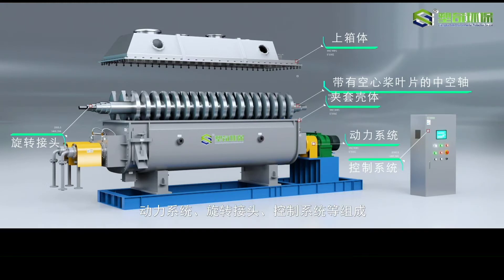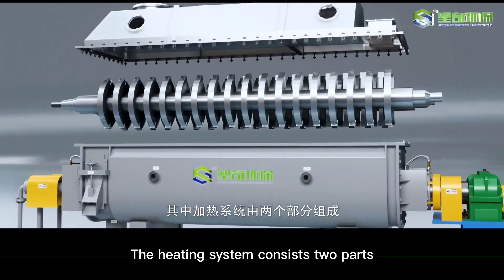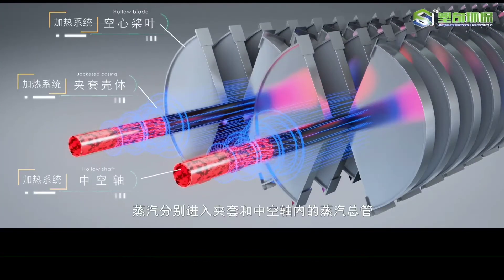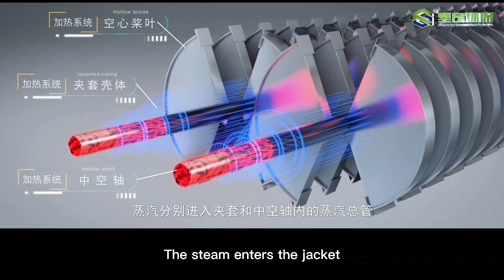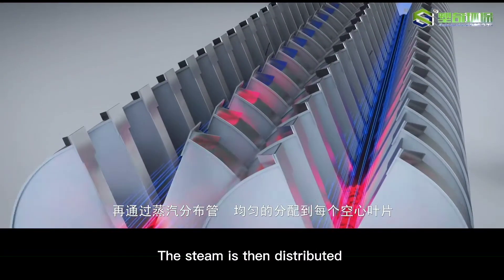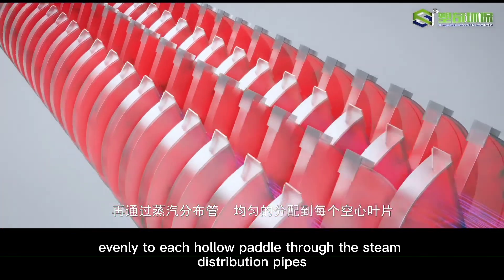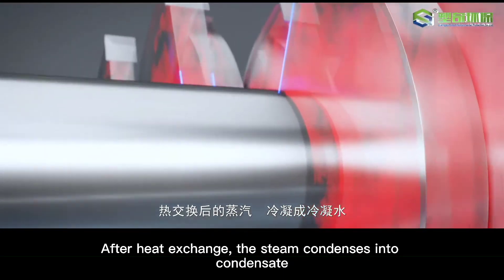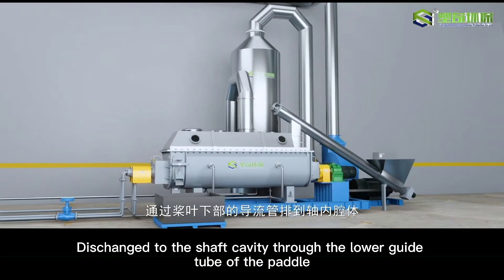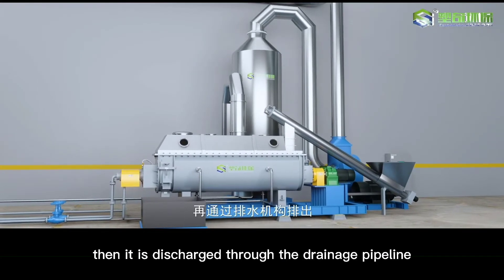The heating system consists of two parts: the jacketed casing and the hollow shaft consisting of hollow paddles. Steam enters the jacket and the steam main pipe inside the hollow shaft. The steam is then distributed evenly to each hollow paddle through the steam distribution tube. After heat exchange, the steam condenses into condensate, which is discharged to the shaft cavity through the lower guide tube of the paddle, then discharged through the drainage mechanism.